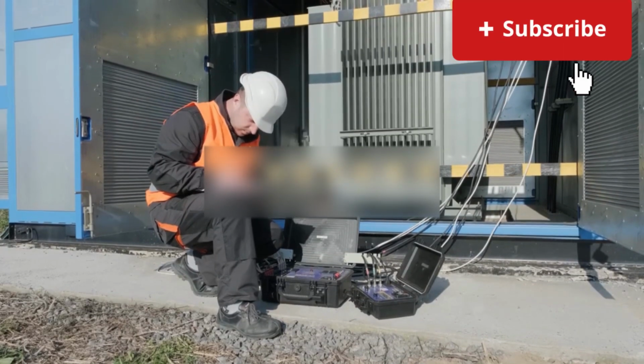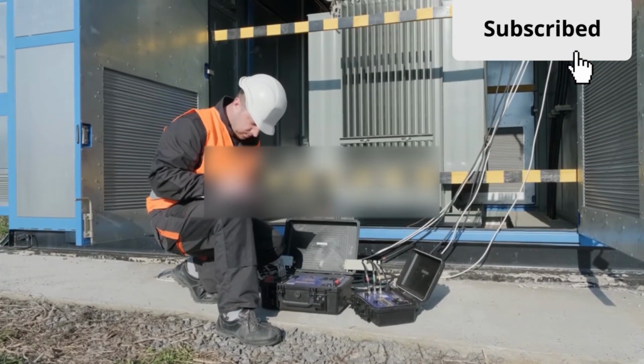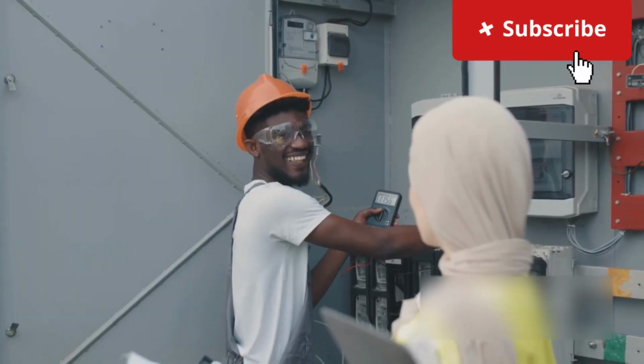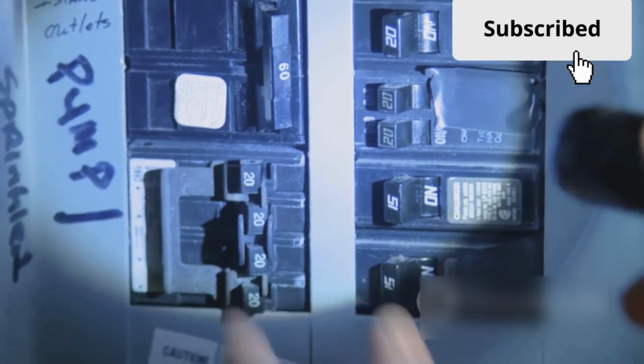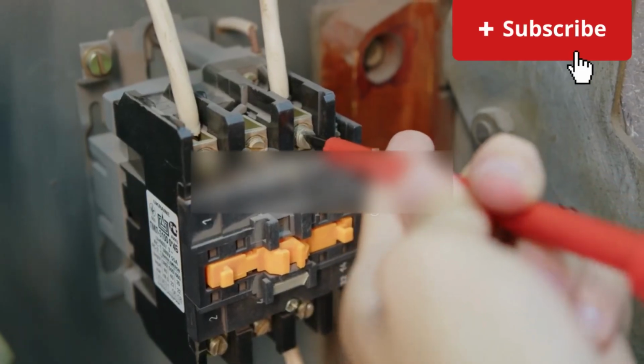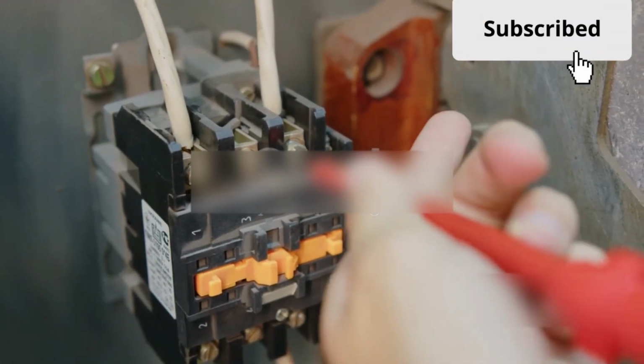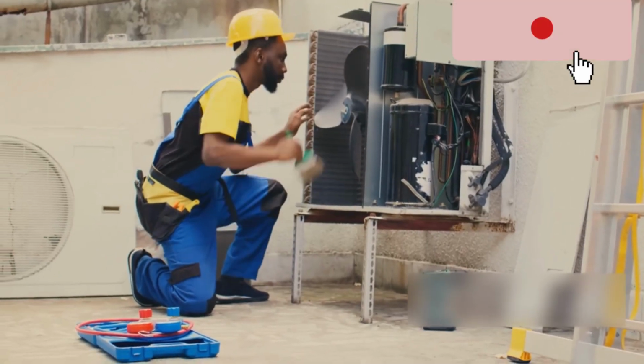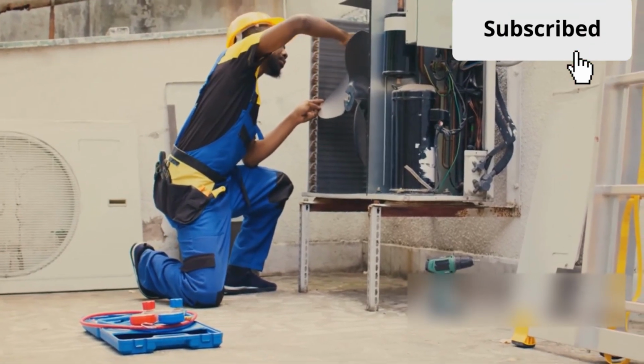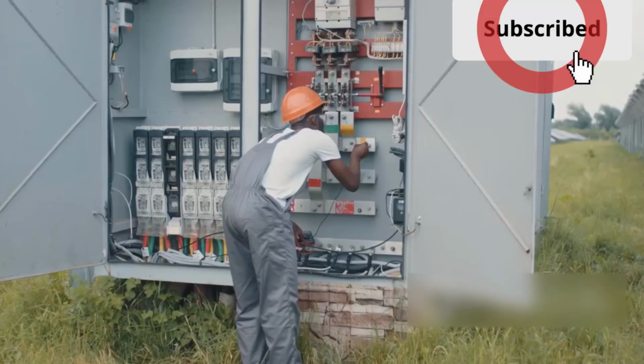Just like any piece of sophisticated equipment, VCBs require regular maintenance to ensure they operate reliably and safely. Don't worry, it's not as complicated as it sounds. One of the most important aspects of VCB maintenance is visual inspection. This involves checking the breaker for any signs of damage, such as cracks, loose connections, or corrosion. Regular cleaning of the breaker's exterior is also essential to prevent the buildup of dust and debris, which can affect its performance. Another crucial maintenance task is contact inspection.